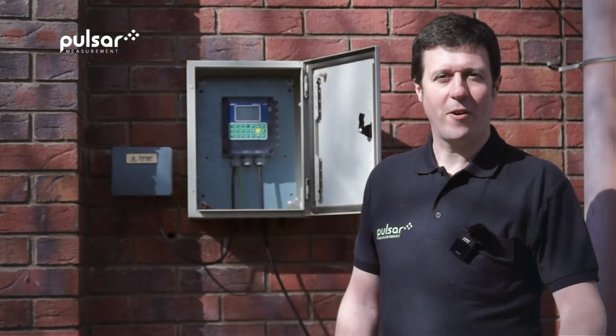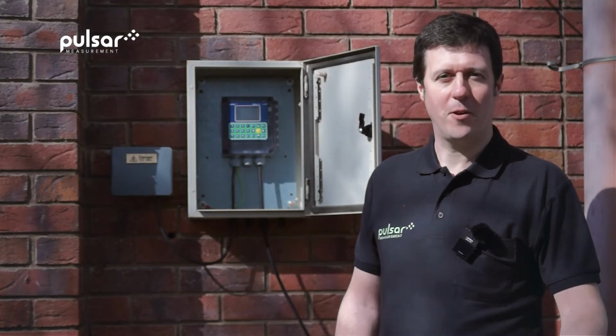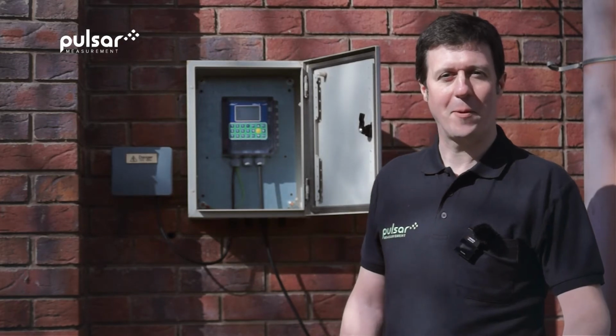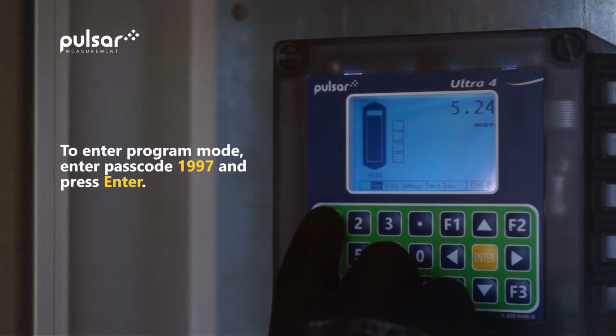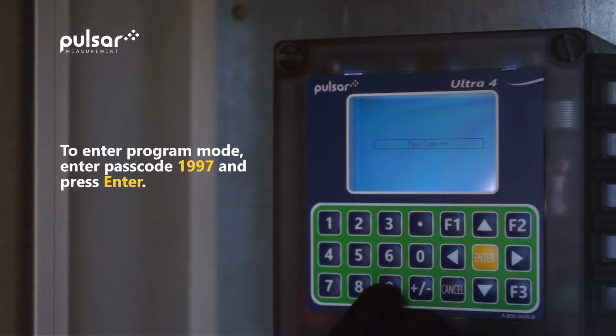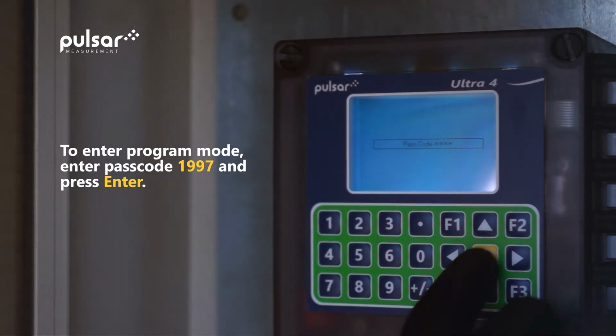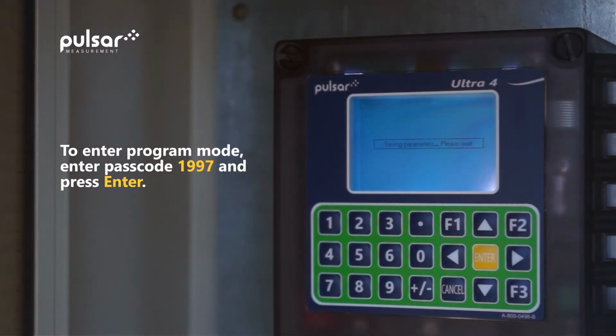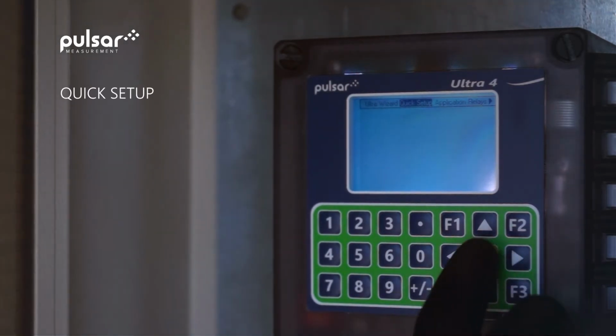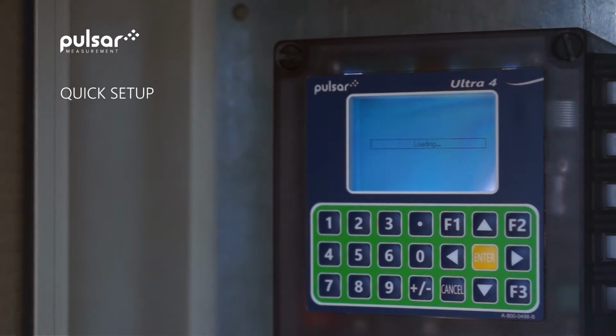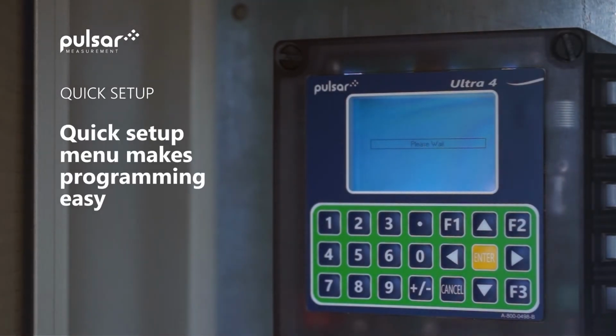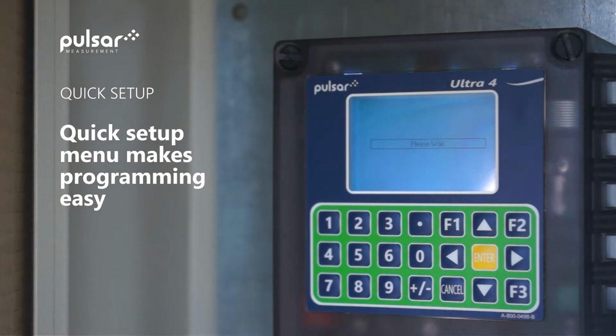The transducer is already connected and the Ultra 4 is powered up and ready to go, so we can start programming. We can enter program mode by entering this passcode 1997 and pressing enter. We'll use the quick setup menu, so we can press enter and enter to enable it. The quick setup menu just asks for required information to make the measurement. We can use the arrow keys and enter to select an option, and use the numeric keys to enter measurements and dimensions.